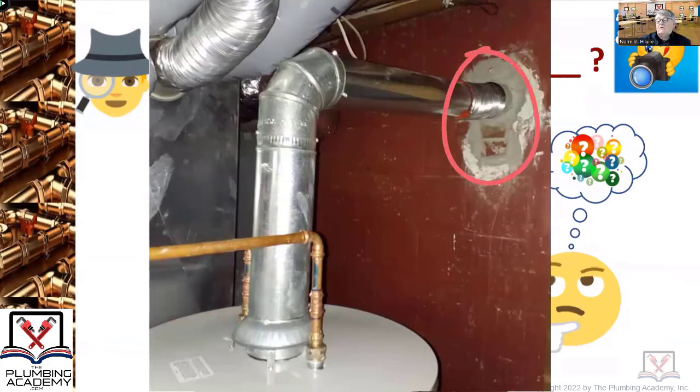It is a chimney that was exposed to the outside — blew a huge hole in it — and then they filled it in and did a decent job fixing everything. It's actually sleeved properly: the liner is dropped down the chimney and it has a cap on the top. Something is missing, even though this is a really good job. There's a thimble coming through the wall and a liner coming through it, so if the liner failed, they could just yank it out and pull a new one in without blowing holes in the wall.